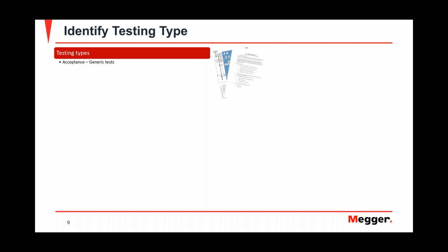Acceptance testing is one of the types of testing that you would do to a relay, which mainly has to do with making sure that the relay that got shipped to the customer fulfills the expectations from the specifications that the buyer provided. For something like this, you usually test your inputs, your outputs, your communications. You would do basic element testing, maybe. These procedures are usually the ones supplied by the relay manufacturer, so they're very basic, and you could do a quick bench test. It's not a big deal.